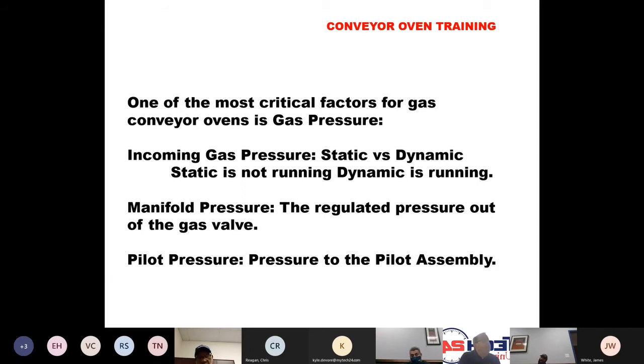Most manufacturers are going to tell you you need to have a minimum of 7 inches of water column on natural gas coming in as a dynamic pressure. If you get much more below 7 inches, you may start to run into gas volume problems.